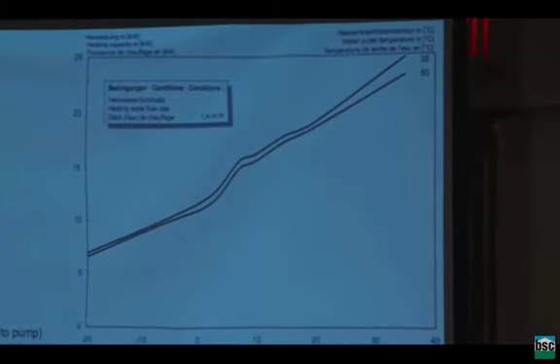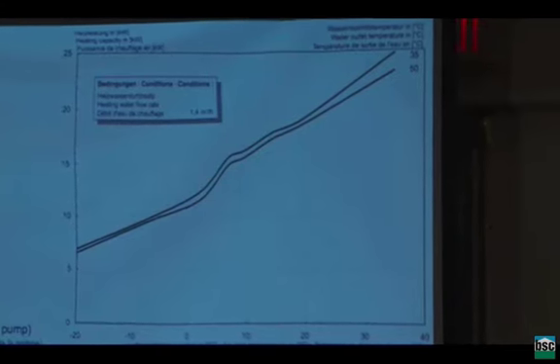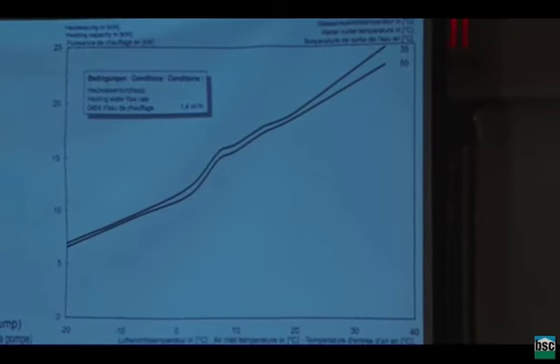And capacity drops pretty quickly as well. That's the upper right-hand corner. It's the capacity in kilowatts, multiplied by 3 point something to get BTUs. And again, the capacity drops off a lot as you get cold. So you have to buy oversized equipment if you're in a cold climate, and that's just to meet the minimum load.